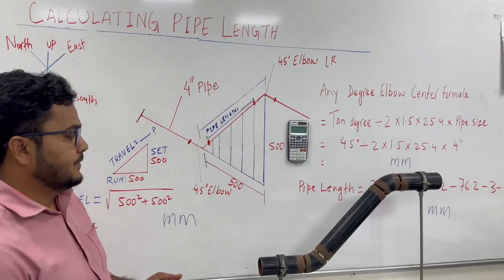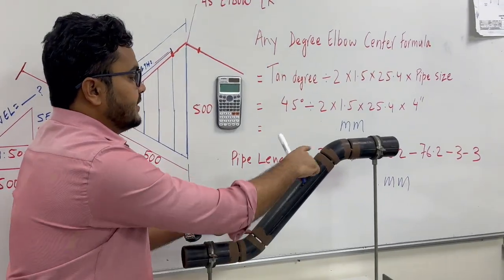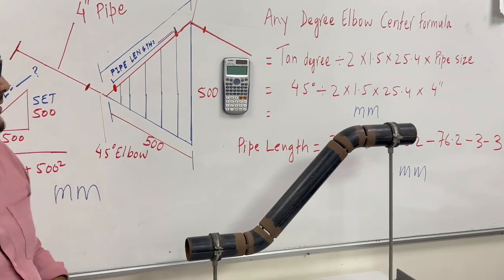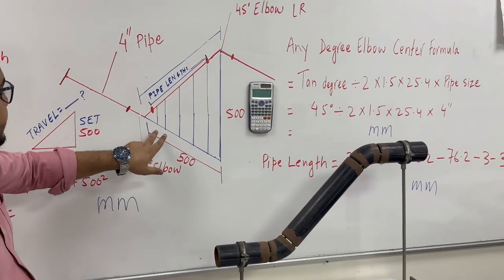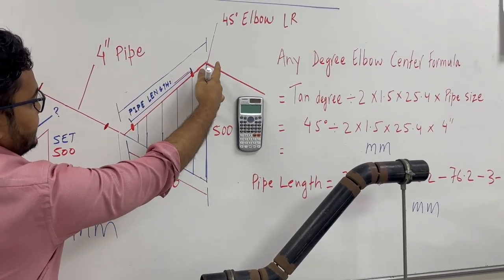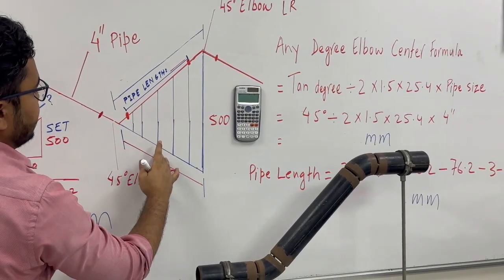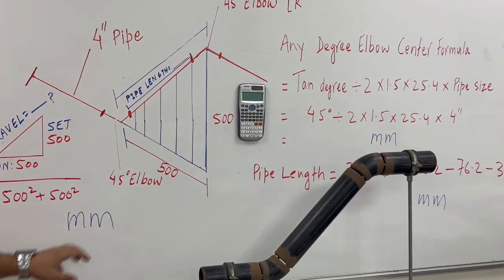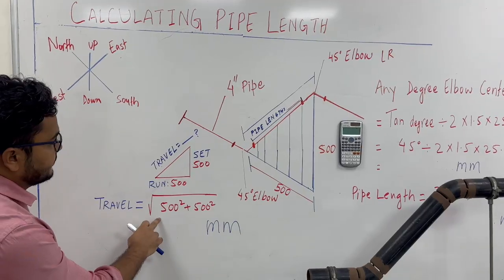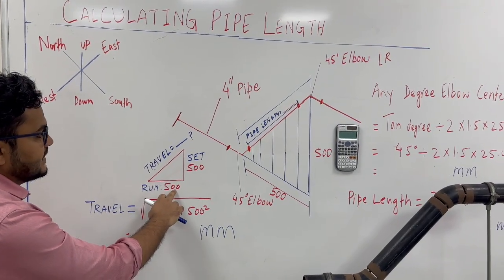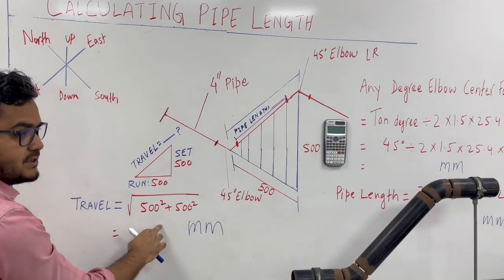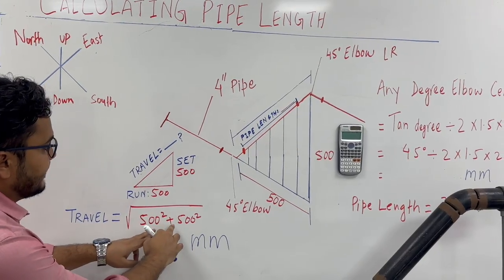We need to calculate this pipeline from here to here. Step by step I will make you understand. We have drawn here a triangle — you can see this is the set, this is called run, and this is travel. We have the formula: travel equals the square root of run squared plus set squared.